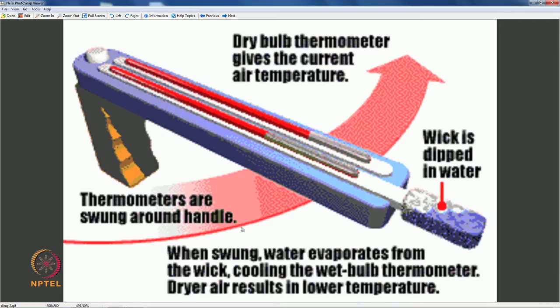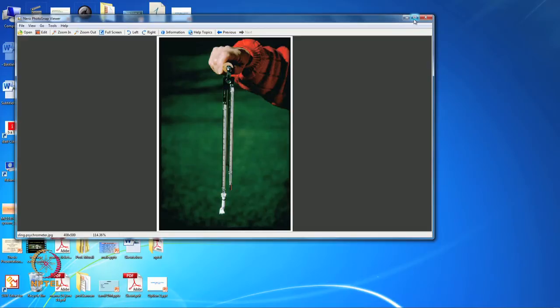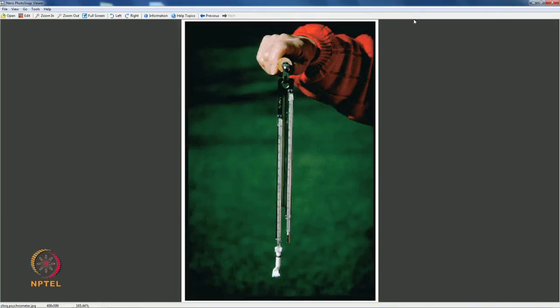This wick is dipped in water and then the thermometers are swung around the handle. You hold it like this and swing it. When swung, water evaporates from the wick, cooling the wet bulb thermometer. Drier air results in lower temperature. There are 2 thermometers — giving wet bulb and dry bulb temperatures. This is the sling psychrometer.